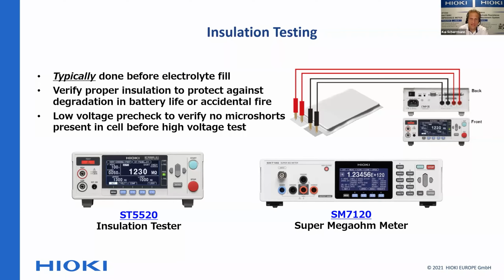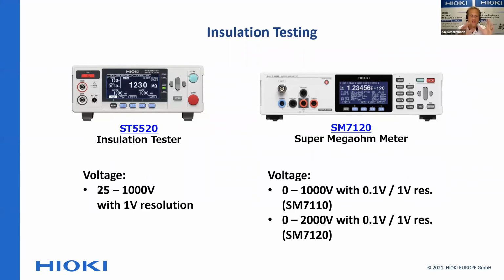And one of the instruments that you can use in a production line to make sure that that doesn't happen is the ST5520 insulation tester. Another option is the SM7120 insulation tester. The most common one is the ST5520. It's the smaller one. Why do I even point out the bigger one? That has several reasons. One reason is that very rarely the insulation voltage or the test voltage of the ST5520, that's only 1000 volts, is not enough. And there are some customers who say 1000 volts isn't enough. And they would then be able to use the SM7120, which allows to go up to 2000 volts as a testing voltage.